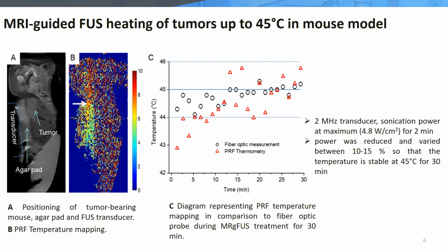Using the 2 MHz transducer, the sonication power was kept at maximum for the first 2 minutes, so that the temperature of the targeted tumor was raised from 37 to 45 degrees. Afterwards, the power was reduced and varied between 10 and 15%, so that the temperature was stable at 45 degrees for 30 minutes.